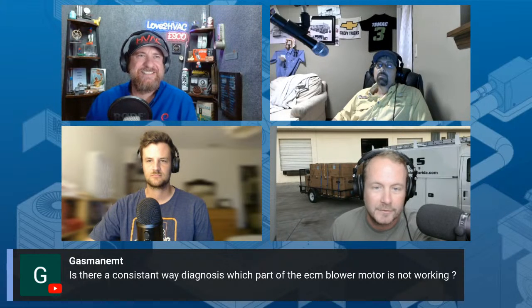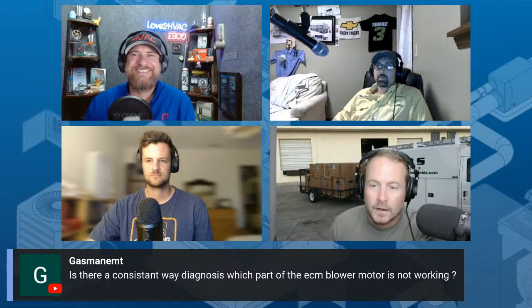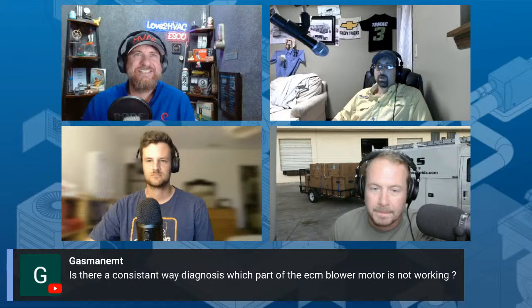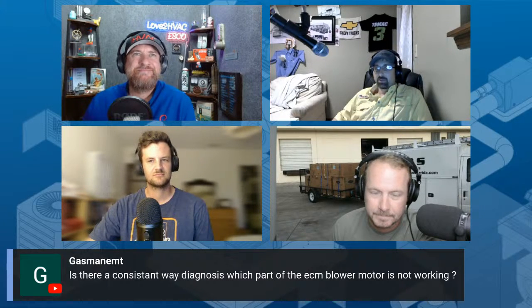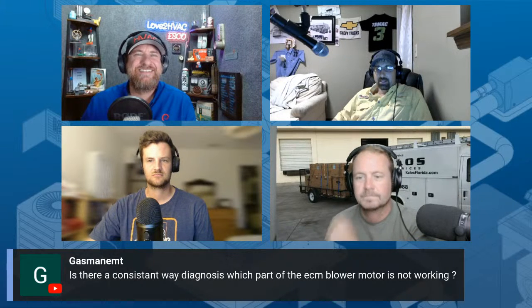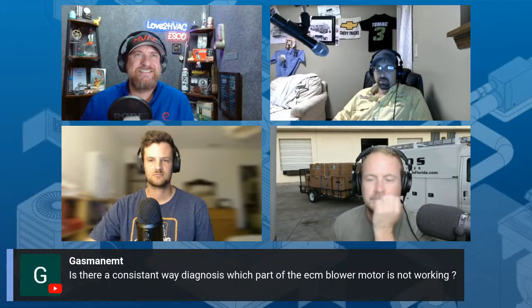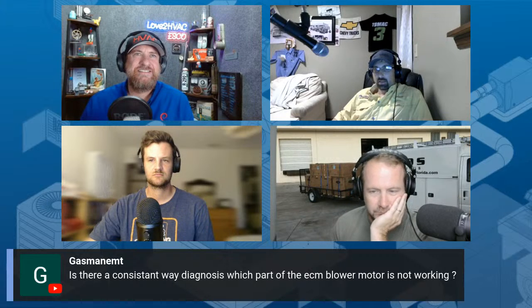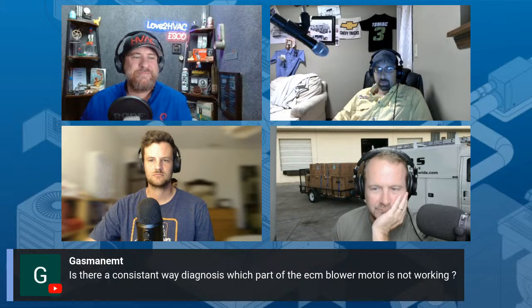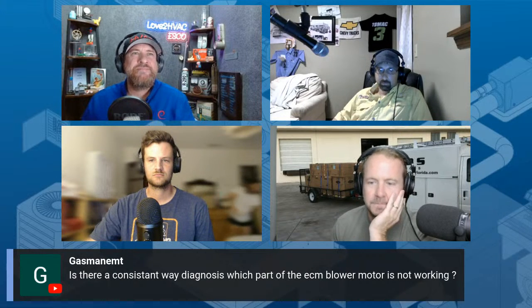Pretty easy diagnosis. And the wheel has to be completely still if you're going to try to ohm out that motor, because even moving a fraction of an inch, your readings jump all over the place and you'll think it's bad. It might actually be better to pull it out of the cage so it's sitting completely still, not attached to a wheel in a cage. Yeah, that is true.